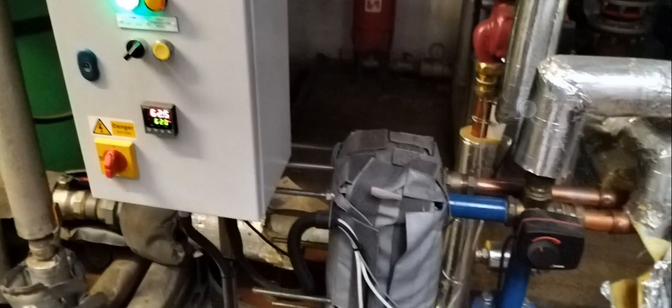So we're having a circulation issue. This pump here that needs changing is at 101 Celsius. The heat isn't getting away from it because it's seized. I start tracing pipework, and this is another view of the plate and the circulation issues.